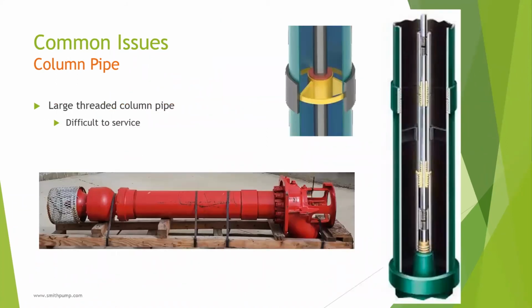Speaking of difficult things to take apart, let's talk about column pipe. Threaded column pipe is the least expensive method for joining column together. However, it should be reserved for small pumps only. We recommend avoiding this method when column pipe is 10 inches or larger and switch over to flange pipe. Threads can rust together and become very difficult to unscrew during disassembly. If that happens, we break out the torch and remove the offending section. It ruins the column pipe, so it's not a preferred way to take apart a pump.